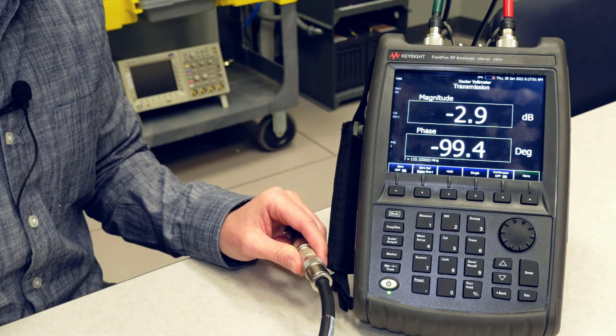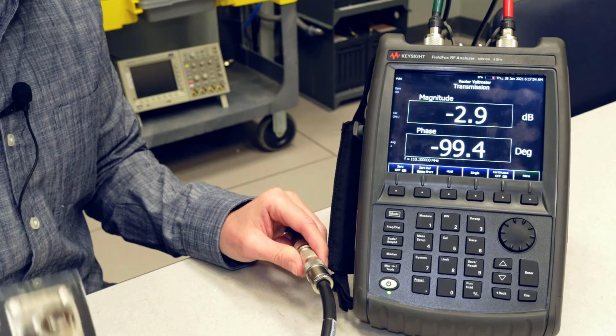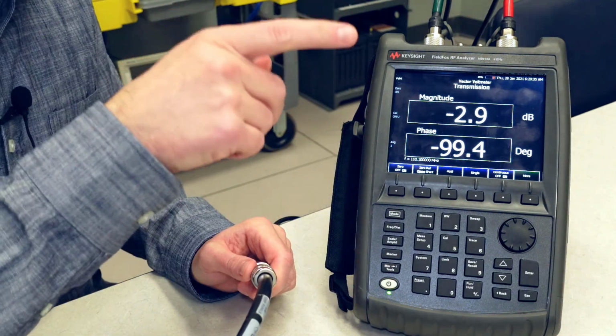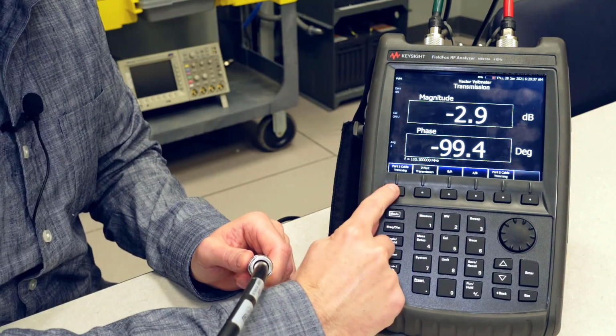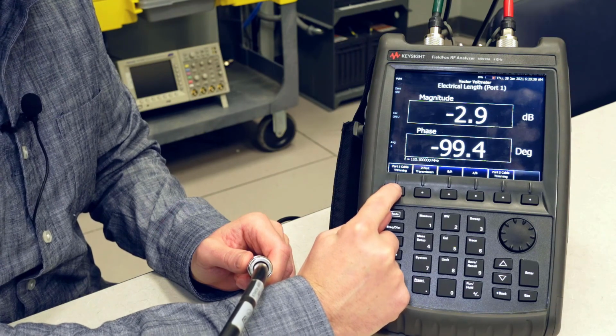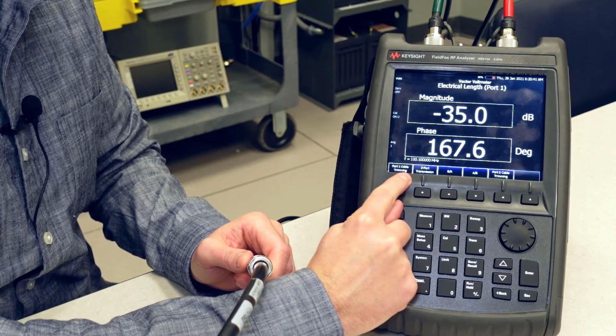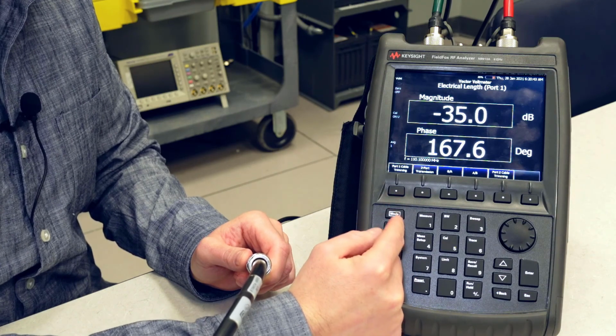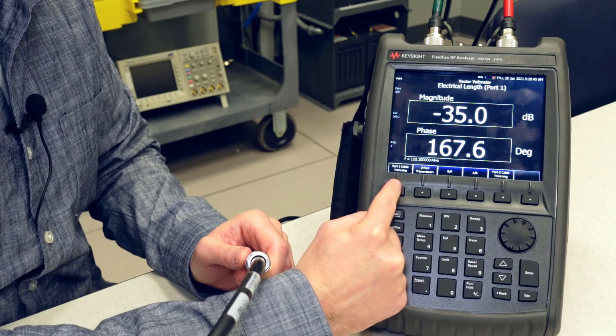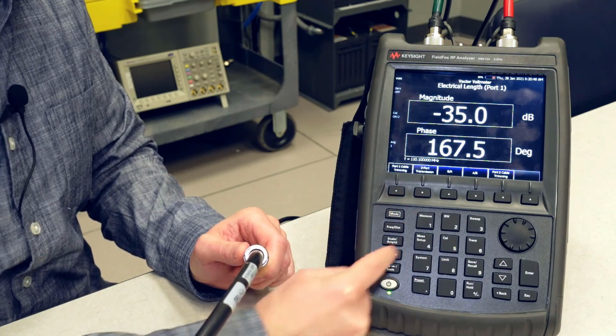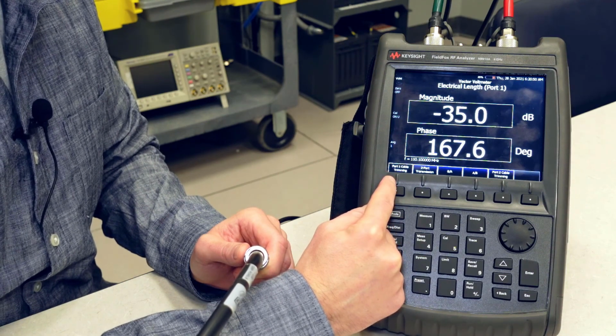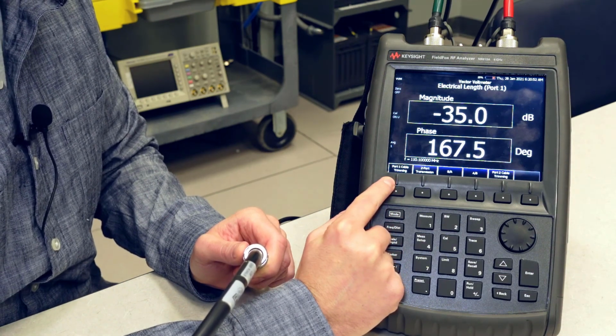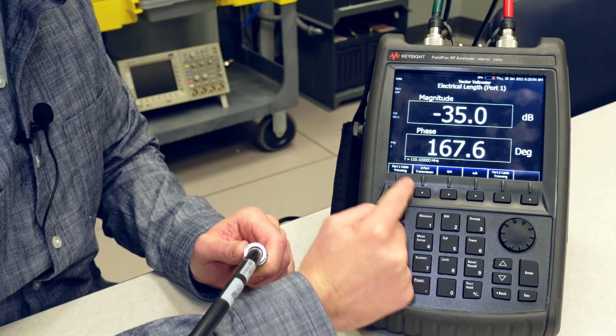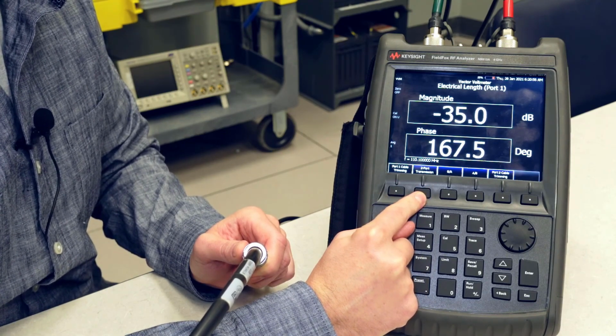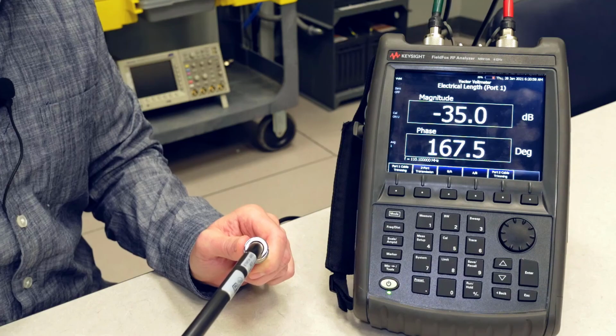Let's go ahead and look at a reflective measurement, like an S11 measurement. In order to do that, we're just going to select measure, and then port 1, which also says port 1 cable trimming. That's not necessarily what we're doing with it, but it's going to serve the purpose for an S11 measurement. So port 1 cable trimming is for reflective measurements, antennas and dummy loads, and port 2 is transmission, which is a little bit more obvious, and it's what we just completed.